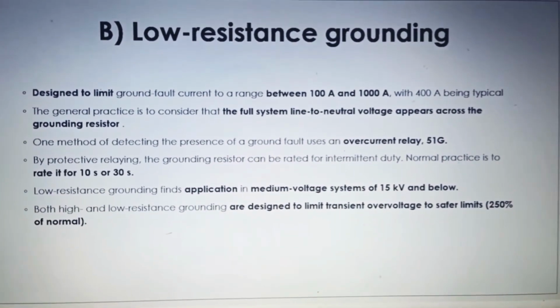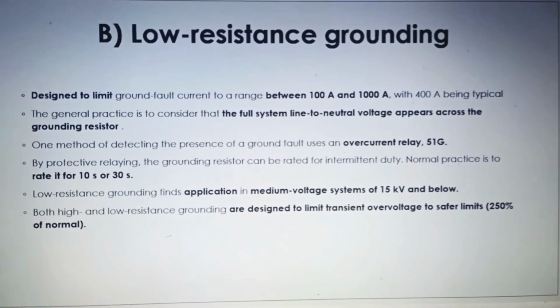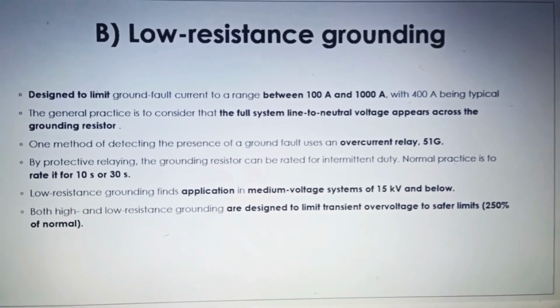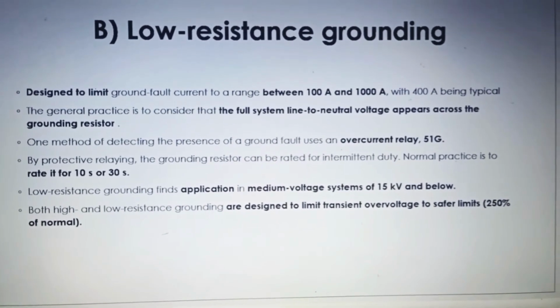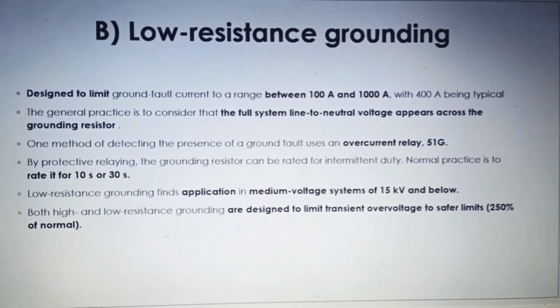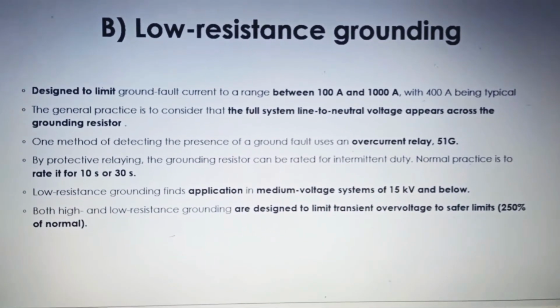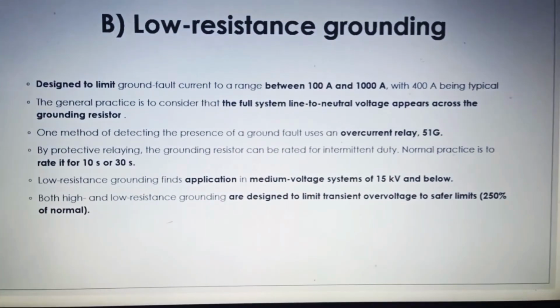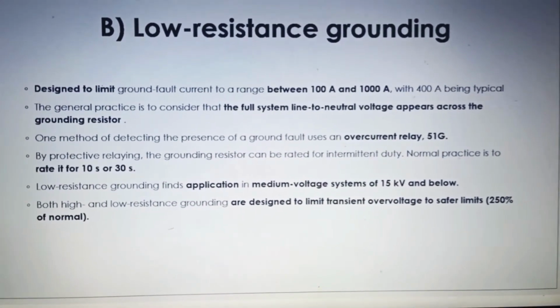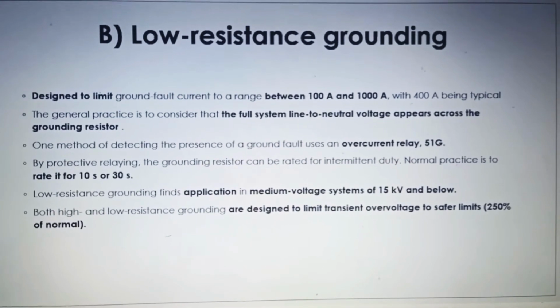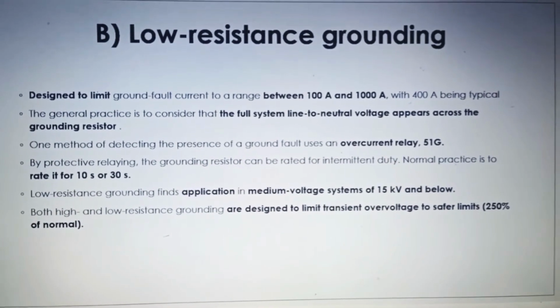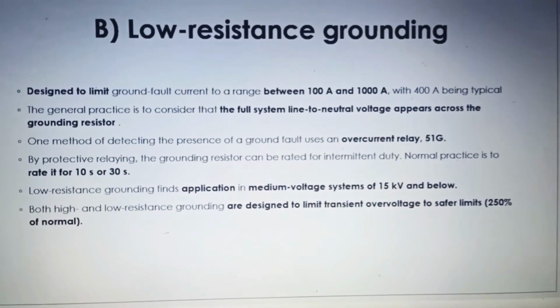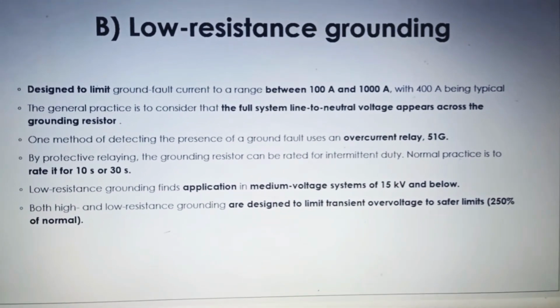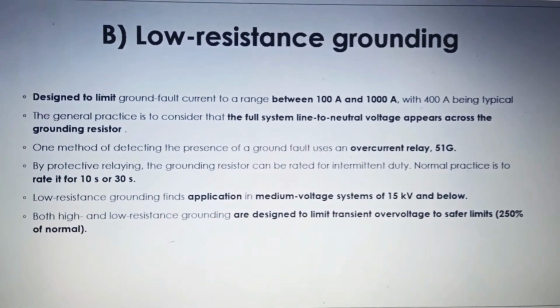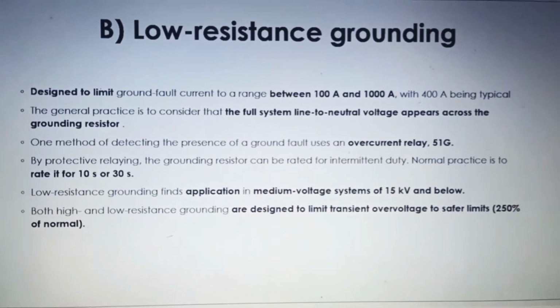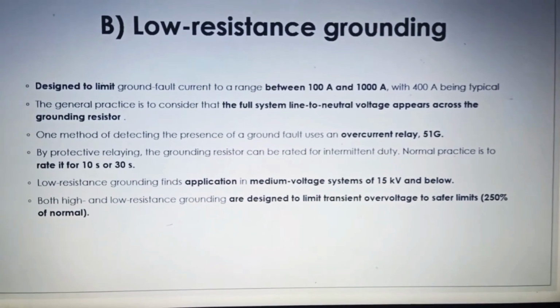Since the combined effect of charging current and the system source impedance will affect the ground current value by less than 0.5% in the typical range of utility supply systems, it is permissible to ignore this effect in calculating the ground fault resistance value. The general practice is to consider that the full system line to neutral voltage appears across the grounding resistor. Only in the case of systems supplied by small generators should departure from this general practice be considered.